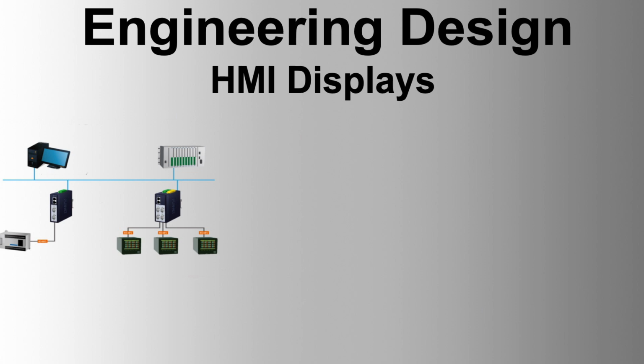Trend group displays trend data for instrument tag parameters pictorially using multicolored trend pens. Each display can show up to 8 trend pens. Trend groups are categorized based on the sampling period and history duration, such as high-speed trends for critical monitoring, medium-term trends for general purpose, and long-term trends for plant performance.